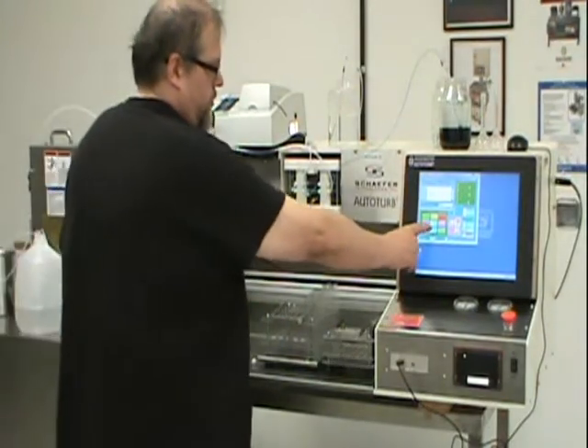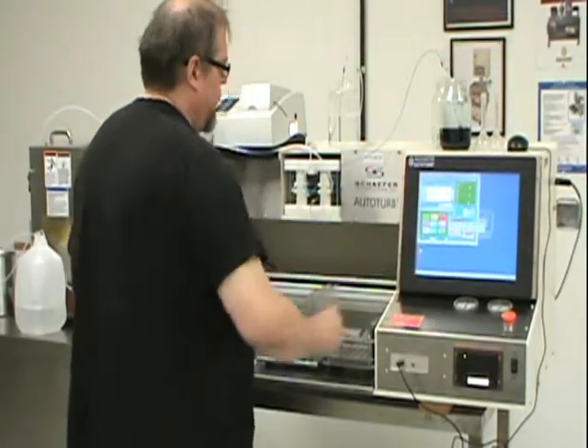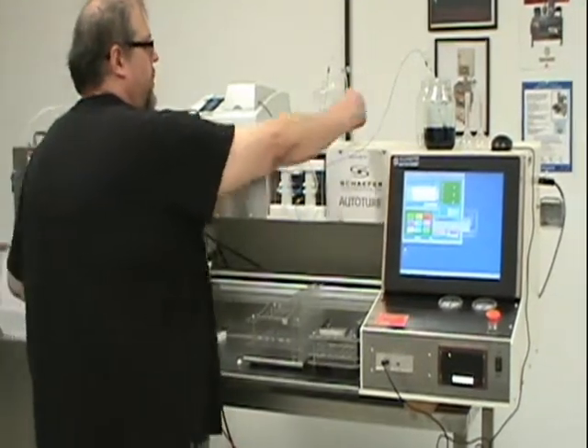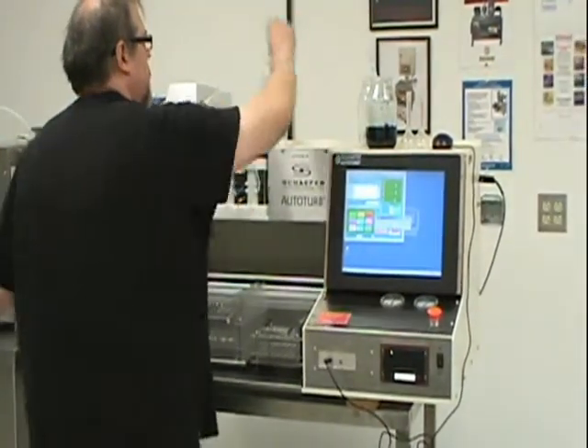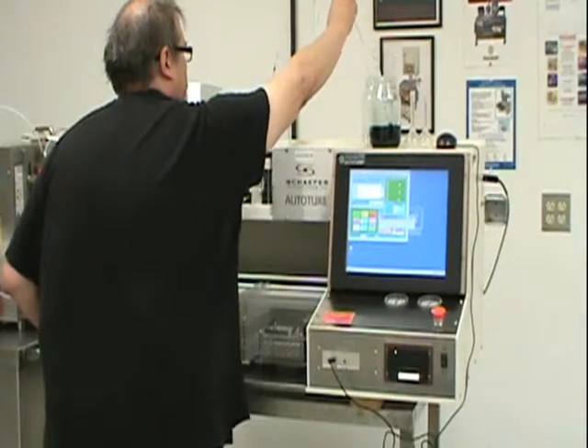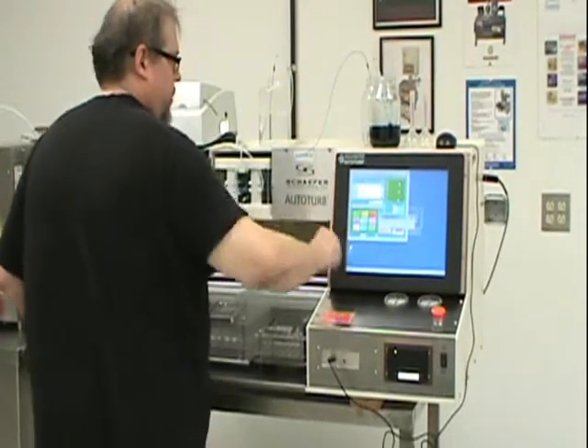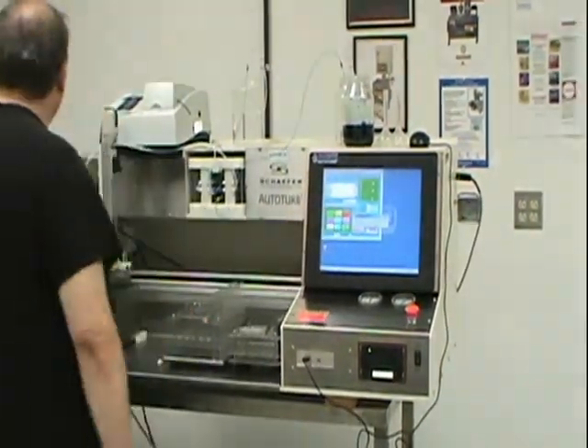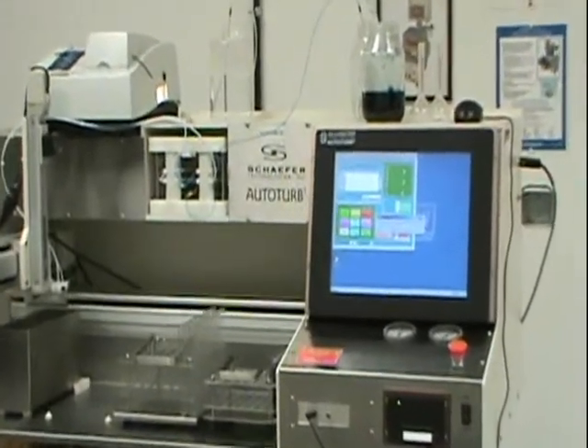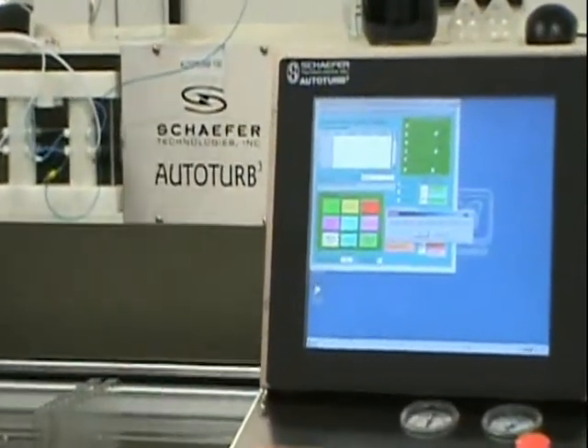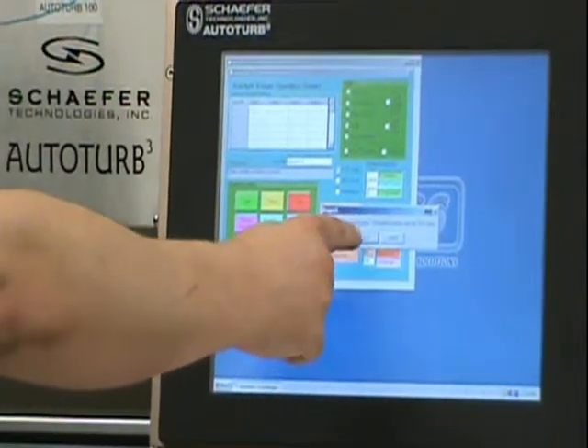That's done, I'd like to go down and do a flush valve, which flushes this system out, switches back to the water. And it also cycles the syringe pump. Now that we know that the valve is shifting fine, we won't have any back pressure issues.